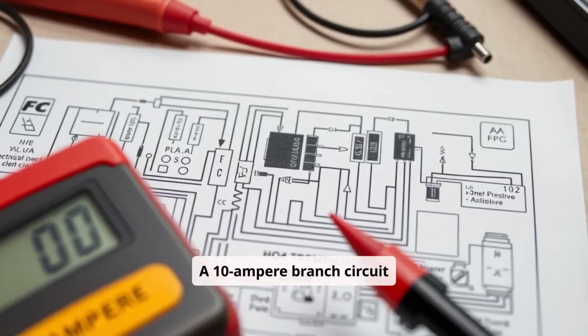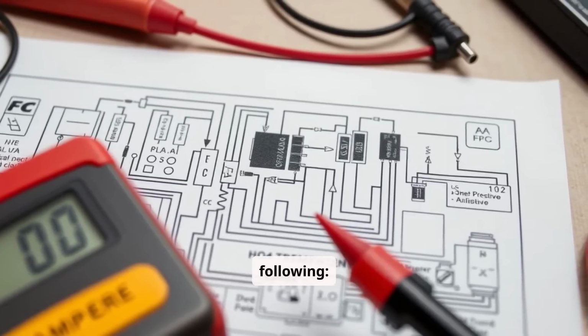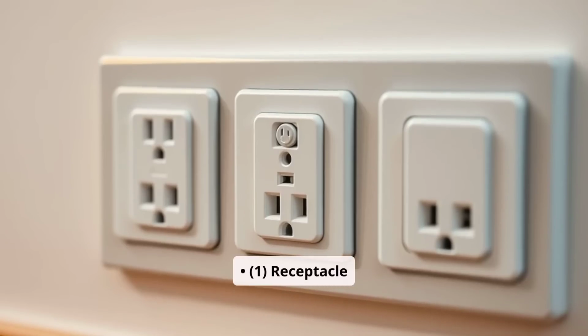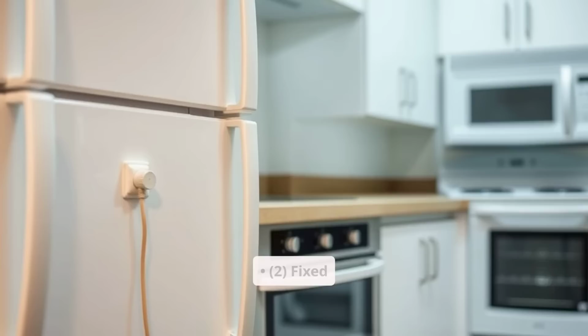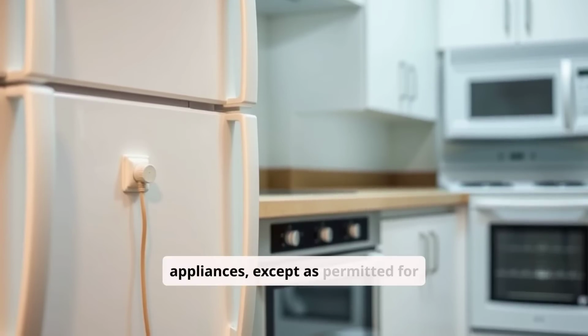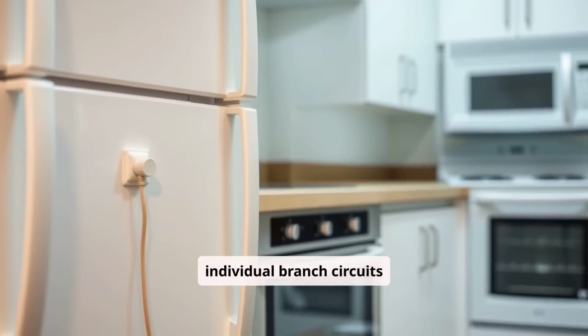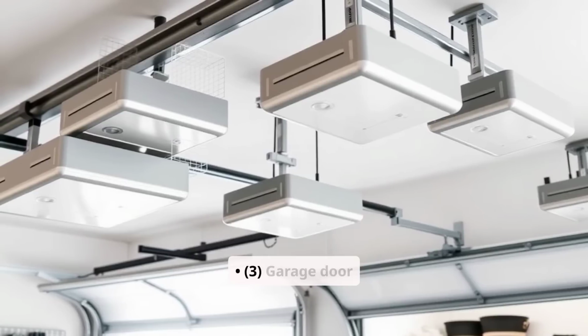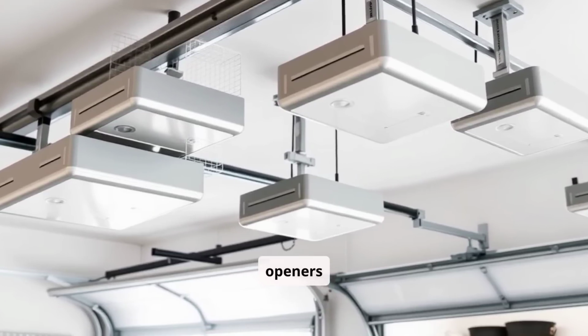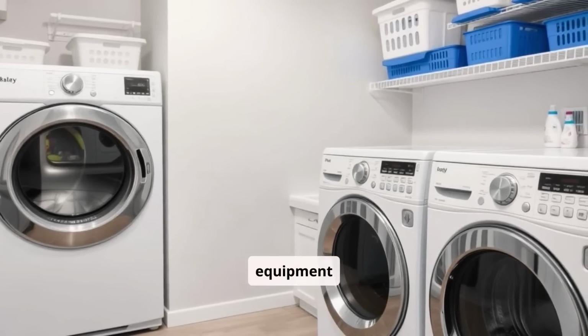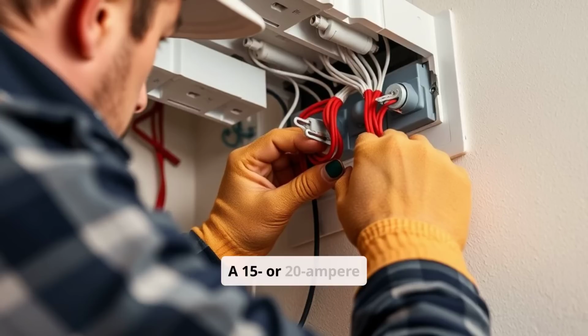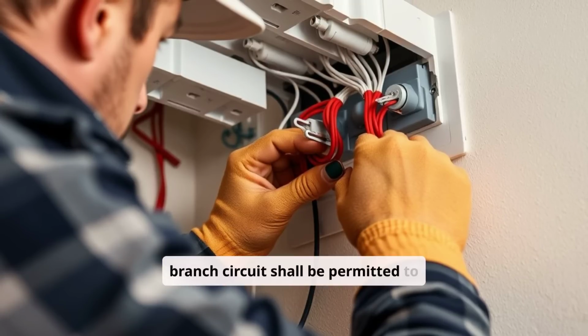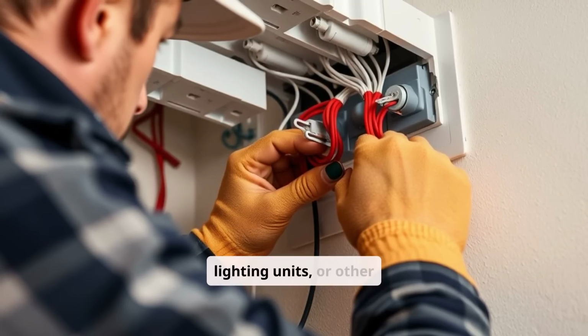A 10 ampere branch circuit shall not supply any of the following. 1. Receptacle outlets. 2. Fixed appliances, except as permitted for individual branch circuits. 3. Garage door openers. 4. Laundry equipment.